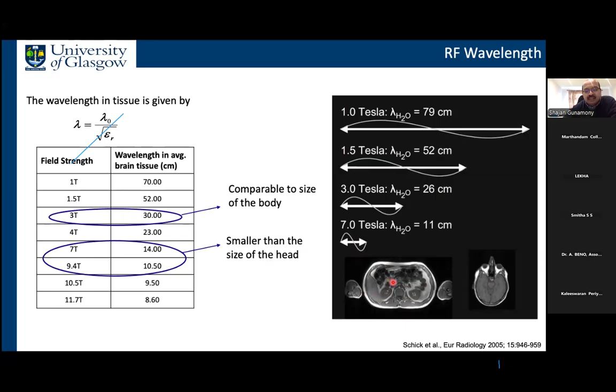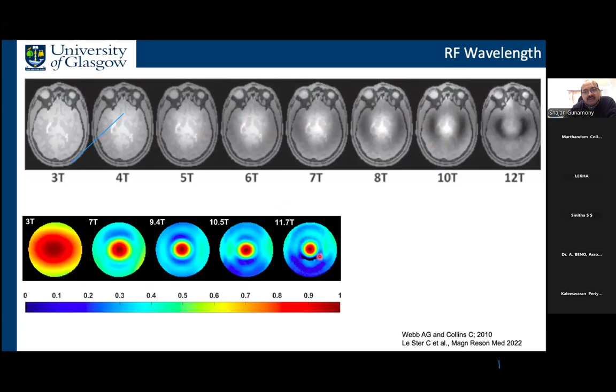So you can see this again here. When you go from 3 Tesla to 12 Tesla, for example, at 3 Tesla, you have a very homogeneous image, and this homogeneity decreases as we increase the field strength. You see this typical center brightening effect, and then there is cancellation in the periphery. You can also see this in a different way here. This is the field produced by the coil. At 3 Tesla, it's quite homogeneous. And then you have this center brightening effect, and then you see the dark ring. At 11.7 Tesla, you see 2 of those dark rings.